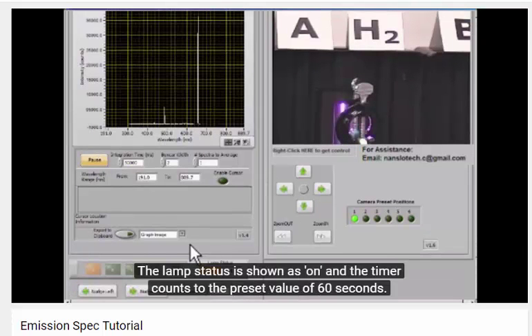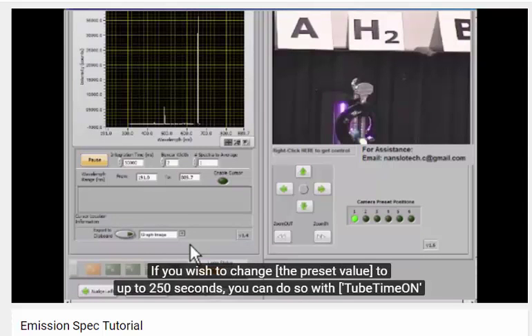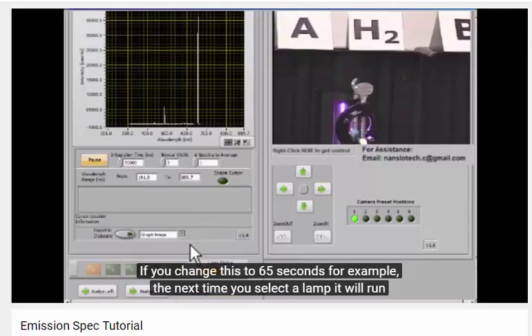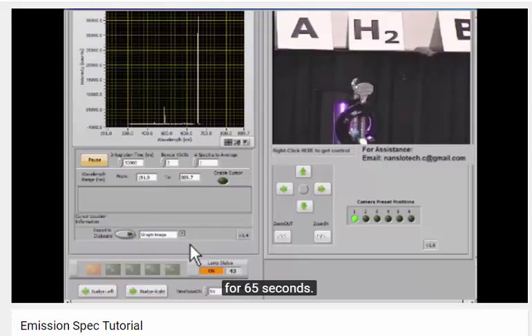The lamp status is shown as on, and the timer counts to the preset value of 60 seconds. If you wish to change this to up to 250 seconds, you can do so here with this field. If you change this to 65 seconds, for example, the next time you select a lamp, it will run for 65 seconds.